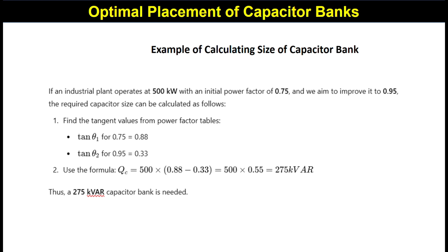The tan θ1 value for 0.75 and tan θ2 value for 0.95 are 0.88 and 0.33 respectively. The active power P is 500 kW. Using the formula: QC = 500 × (0.88 − 0.33) = 500 × 0.55 = 275 kVAR. Note: you must find θ1 by computing cos⁻¹(0.75) and θ2 by computing cos⁻¹(0.95), then take the tangent of those angles. A common mistake is taking 0.75 and 0.95 directly as the angle values, which gives a wrong result.